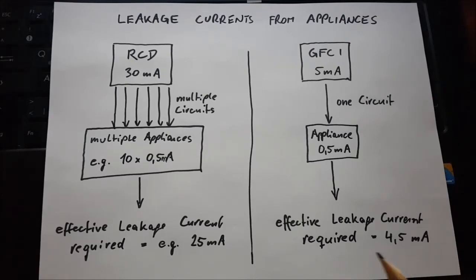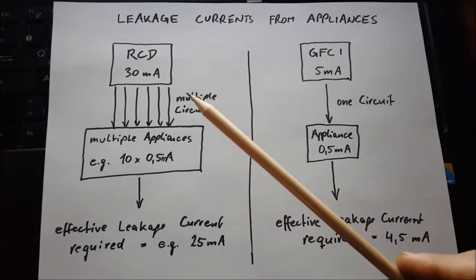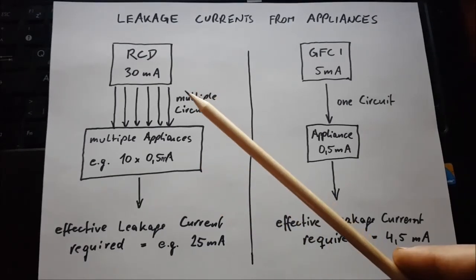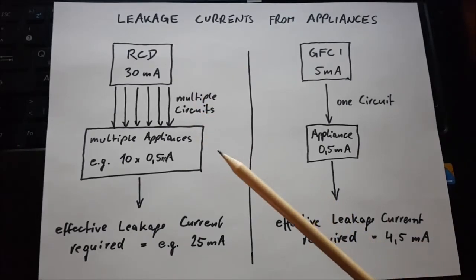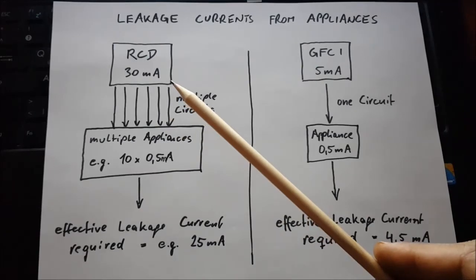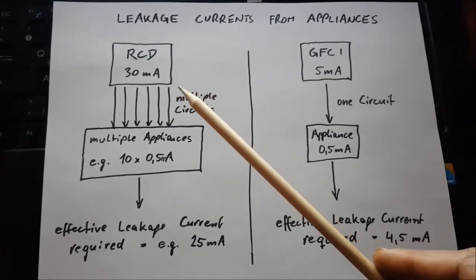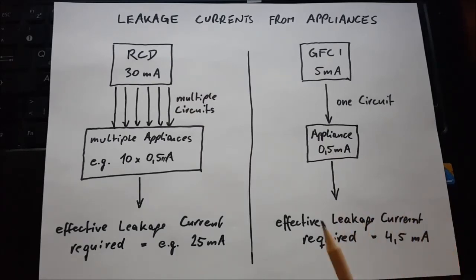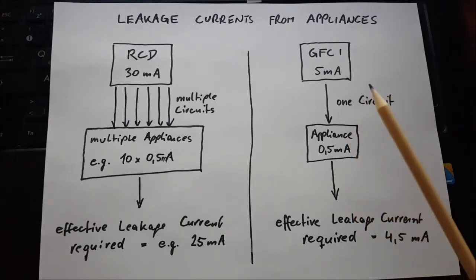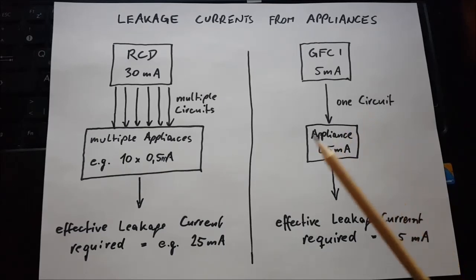So you can see that the more appliances you have, on one side you have to, of course, be aware that if there's too many circuits behind the RCD, too many appliances, that RCD could trip, and we actually don't want it to trip yet. So in this case, it might be even necessary sometimes to split the circuit into two RCD circuits or more. This problem we do not have with GFCIs because, as I said, typically one GFCI will only be there for one appliance, one circuit.